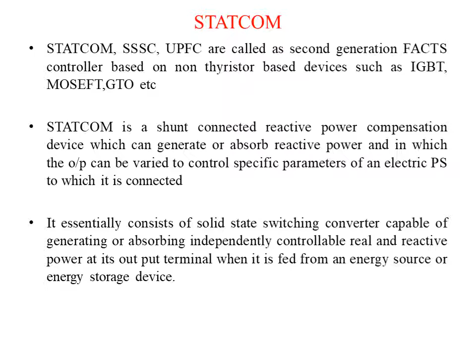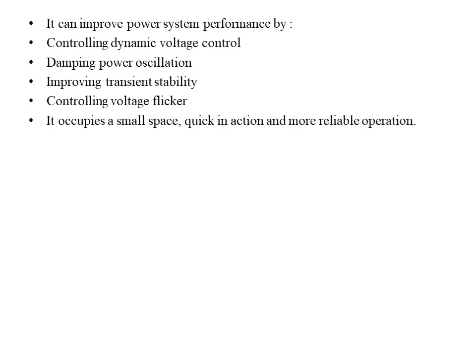In this way we can have control depending upon the voltage generated across the static compensator as well as the voltage of the transmission line. So in this way we can control the operation of compensators. It can improve the power system performance by damping voltage, dynamic voltage control, damping power oscillations, improving transient stability, controlling voltage flicker, etc. It occupies small space, is quick in action, and has more reliable operation as compared to TSC-TCR, where we have slower switching operation, but in case of STATCOM, the switching operation is fast.